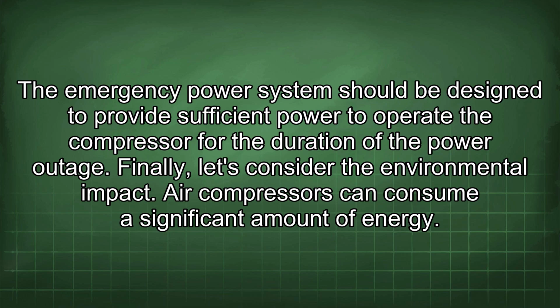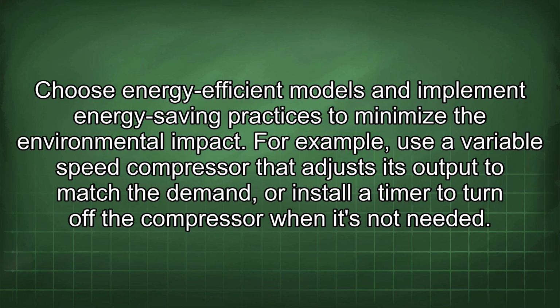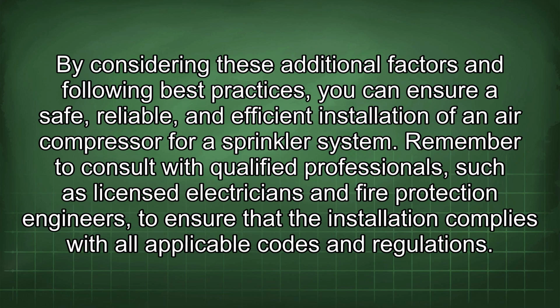Air compressors can consume a significant amount of energy. Choose energy-efficient models and implement energy-saving practices to minimize the environmental impact. For example, use a variable speed compressor that adjusts its output to match the demand, or install a timer to turn off the compressor when it's not needed. By considering these additional factors and following best practices, you can ensure a safe, reliable, and efficient installation of an air compressor for a sprinkler system.